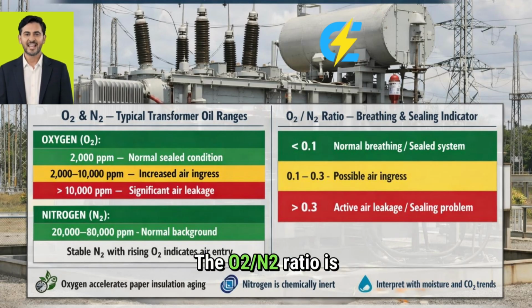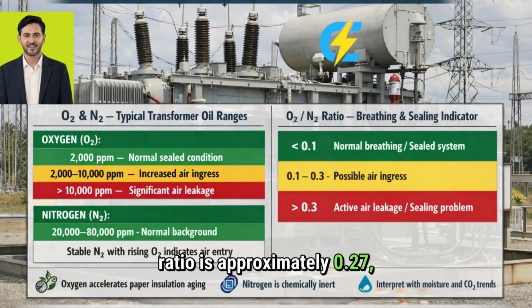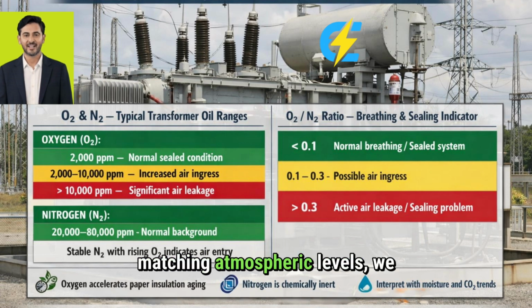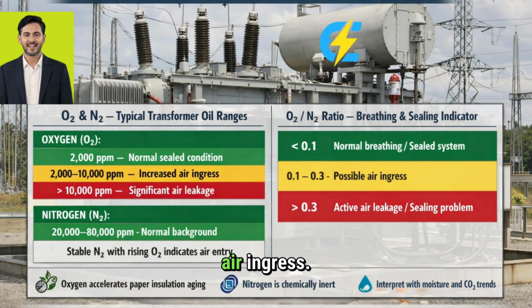The O2/N2 ratio is our key diagnostic tool. In atmospheric air, this ratio is approximately 0.27 based on the 21% oxygen and 78% nitrogen composition. This ratio reveals air ingress severity. When we see this ratio in transformer oil matching atmospheric levels, we know we have active air ingress.